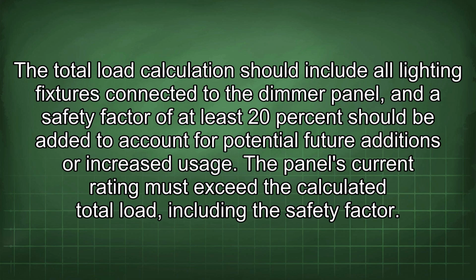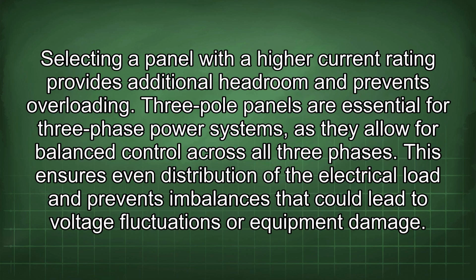The panel's current rating must exceed the calculated total load, including the safety factor. Selecting a panel with a higher current rating provides additional headroom and prevents overloading. 3-pole panels are essential for 3-phase power systems, as they allow for balanced control across all 3 phases.